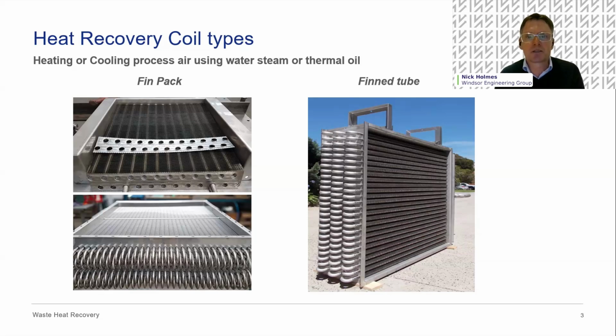So there's two main technologies that go into these heat exchangers. There's a traditional fin tube that people probably have seen around. Typically, that's an extruded fin, so you might have an aluminium fin on a base tube that's either stainless steel or carbon steel. So that's the photograph on the right, and typically that relies on mill manufactured lengths of tube. Whereas on the left, a fin pack. Some people call it a plate fin. It's similar to a car radiator if you think of it like that. So there's a lot of heating surface in the same face area, so they're typically more efficient than a fin tube. There's lots of flexibility in the design in terms of materials for the fin, the materials for the tube. So that top photograph shows you press the fin out of a solid piece, so it's a more robust solution than a traditional fin tube.